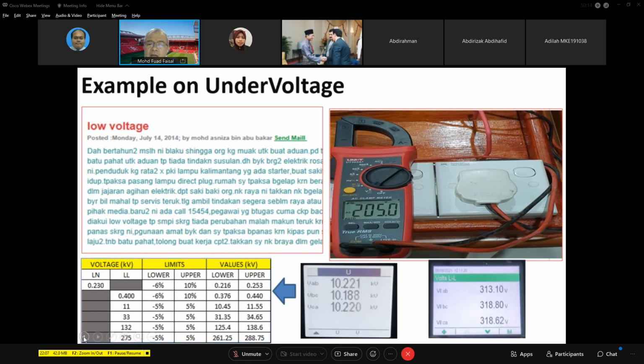If you are a part-time student working with an industry, remember, at 11 kV, the voltage must be 11 kV plus or minus 5%. If your industry is experiencing 10.2 kV, this is under voltage. This must be reported immediately for action to be taken. If you are working with industry or taking LV 400 volt, as you can see here, the voltage shown is only 313, so it's lower than the value.